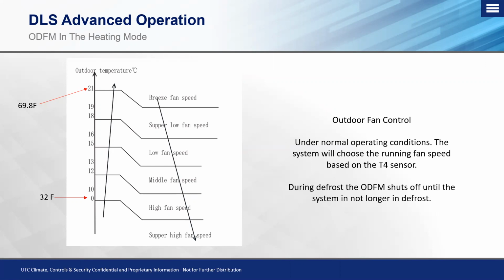Now in this case, you can see as the outdoor temperature rises in the heat mode, the outdoor fan is going to slow down. Roughly at about 70 degrees, we're going to be running that fan at the lowest fan speed setting possible, which is our breeze fan speed. As we decrease in outdoor temperature, at 32 degrees, we're going to see that fan motor running at its absolute highest fan speed. As we drop lower than that, the highest we can go is a high fan speed, so anything 32 and lower, that fan should be in high fan speed operation. Same concept as the cooling, we're just inversing how that fan adjusts to high and low temperatures and what it reacts to.